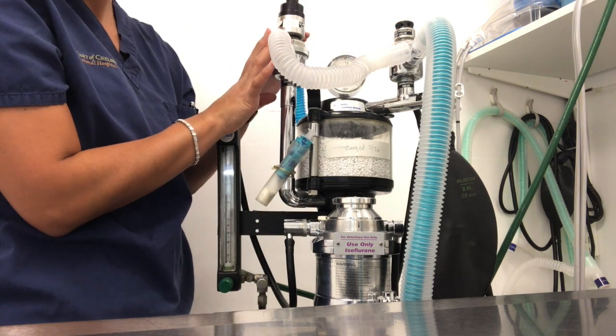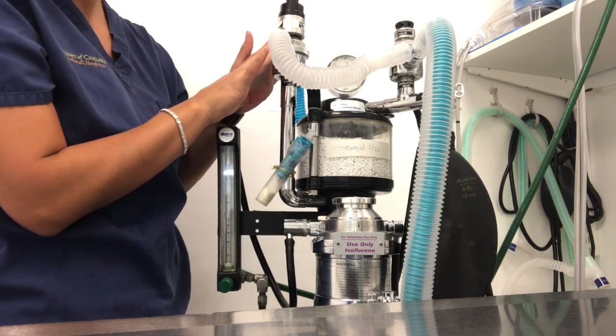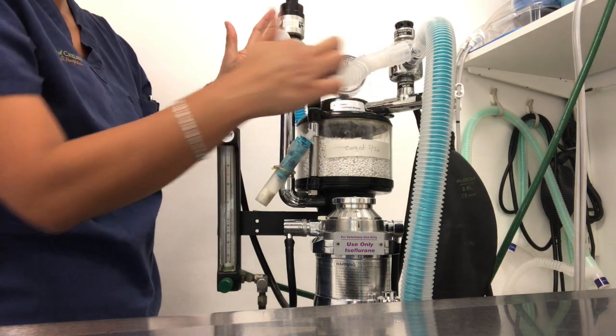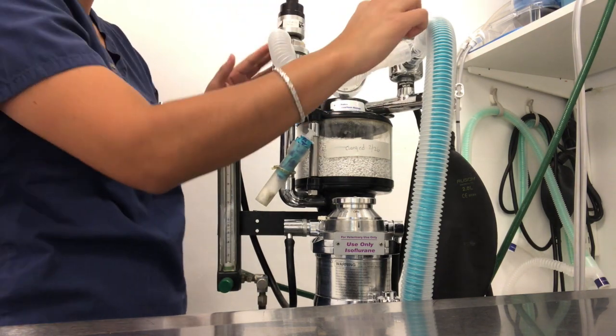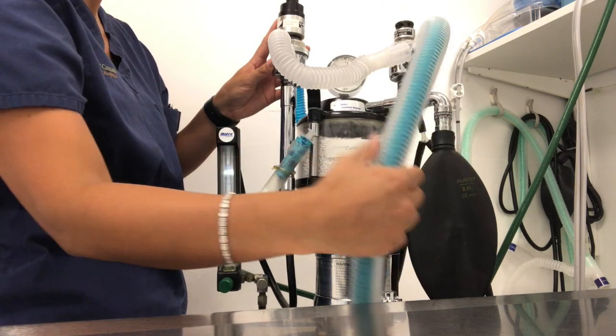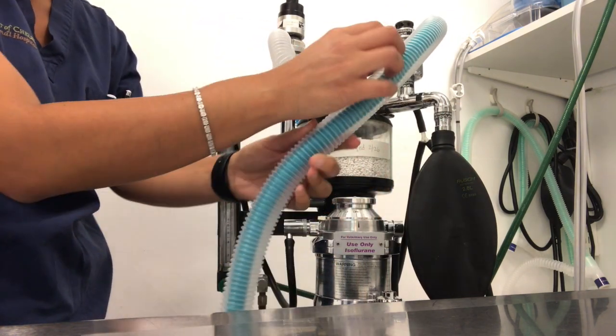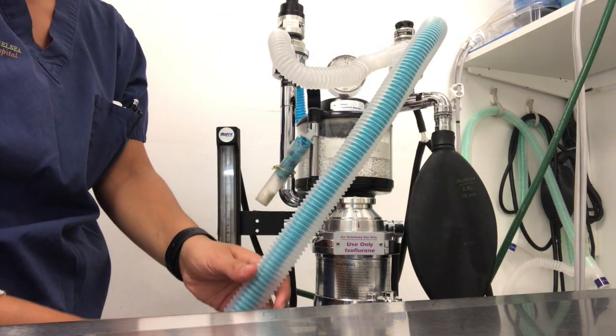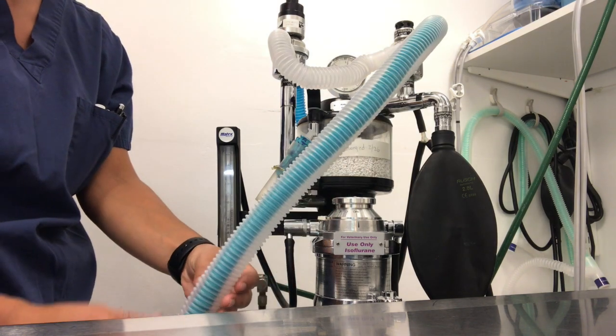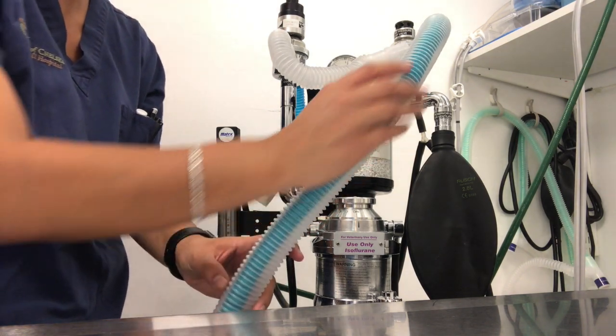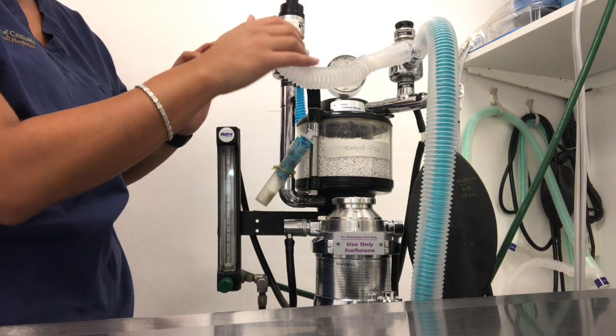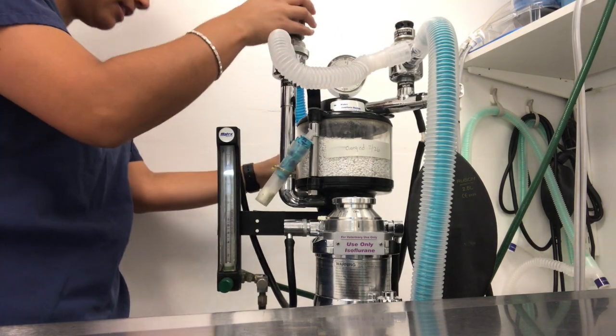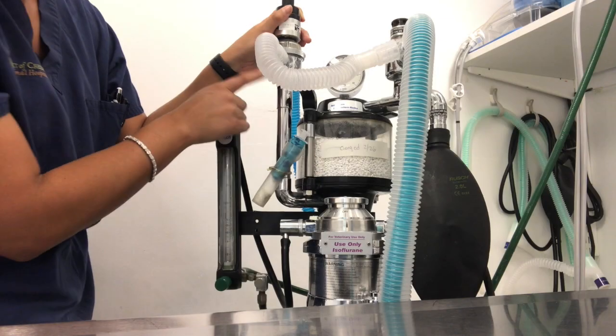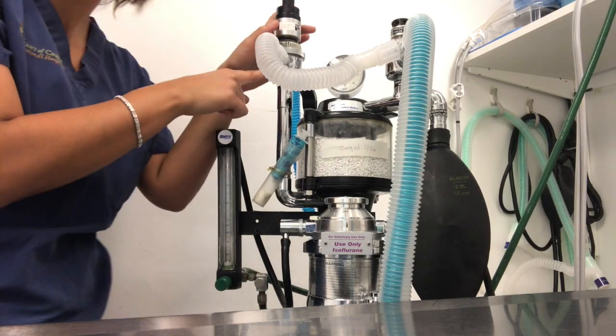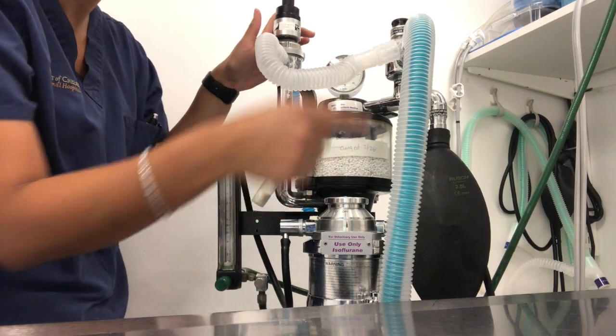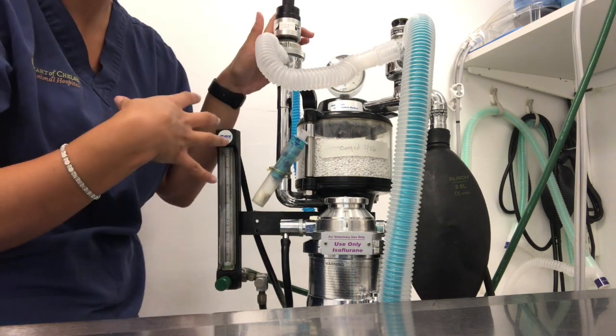Our exhalation valve, which is on the left right here, is the attachment point for the expiratory gases. Our patient will breathe in these gases through our blue tube in here, and then as our patient exhales, it will go out the outside of the tube, this white tube here, and all the exhalation gases will flow into here. So the exhalation valve carries not only carbon dioxide, but also anesthetic molecules that flow back when the patient exhales.